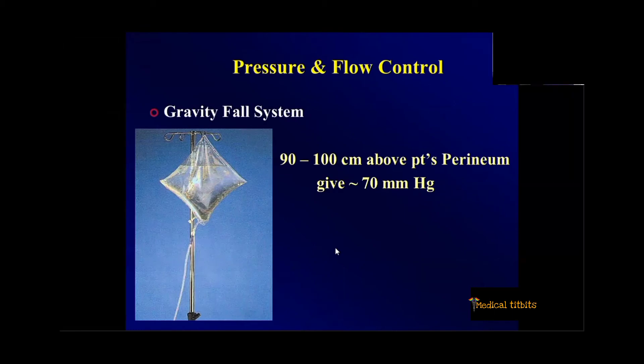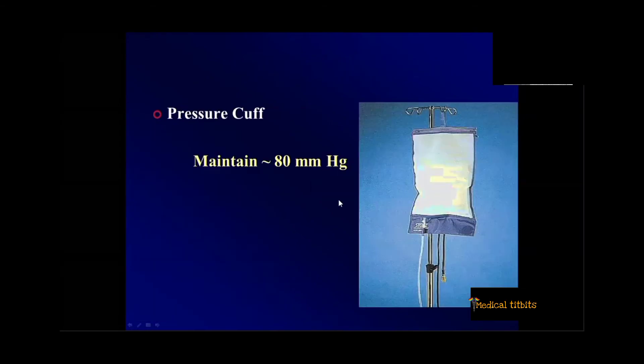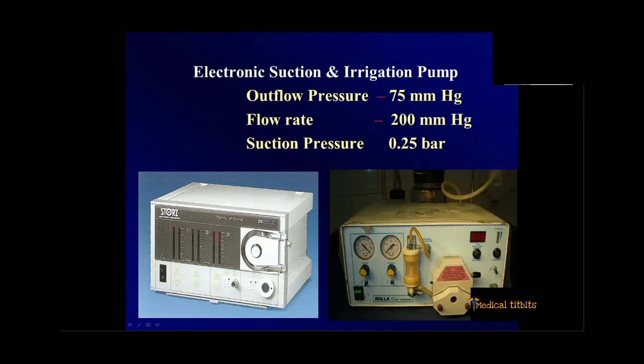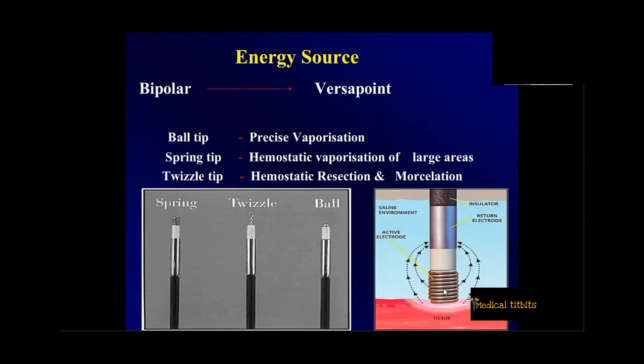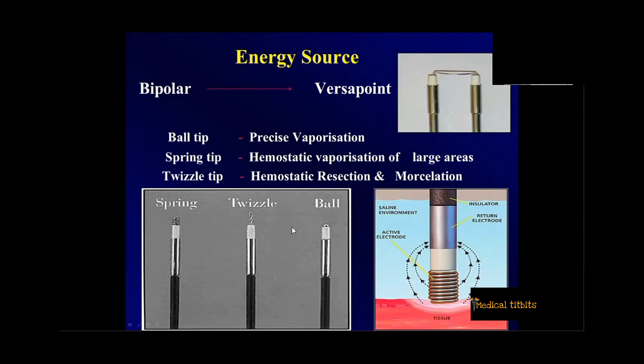Whatever instruments are used, we have to have adequate pressure to distend the uterine cavity. We can use a gravity fall system where the fluid source is more than 1 meter above the patient, giving approximately 70 mmHg pressure, or we can use a pressure cuff. What is recommended is to use a proper hysteromat. The tube is squeezed by a roller ball so pressure won't exceed too much and the chance of air embolism is less — we suck fluid from a closed tube so air embolism risk is reduced. For bipolar energy source, we need not use glycine; the current travels from one electrode to the other.